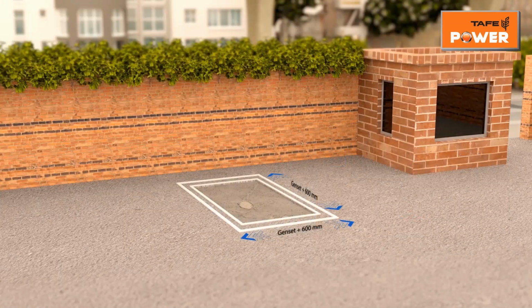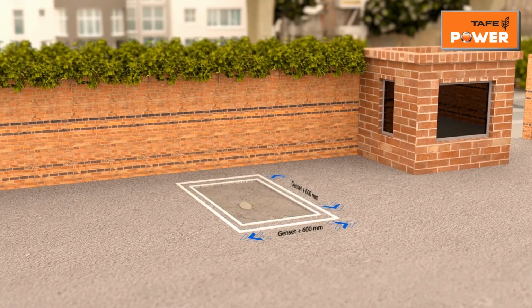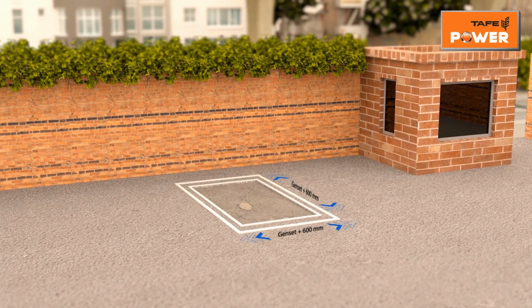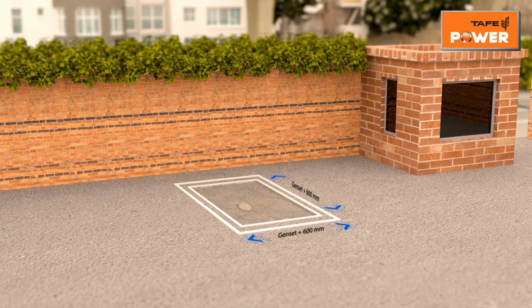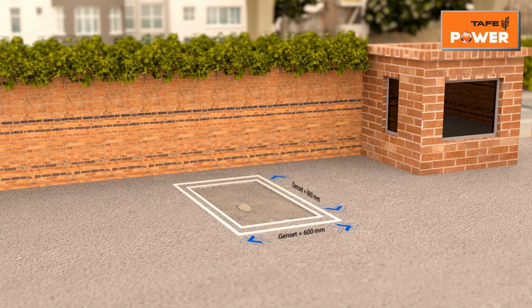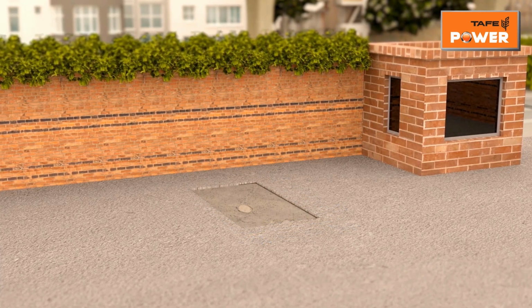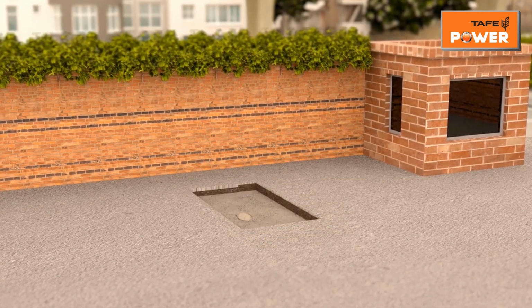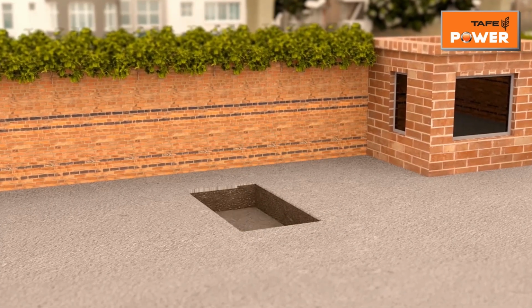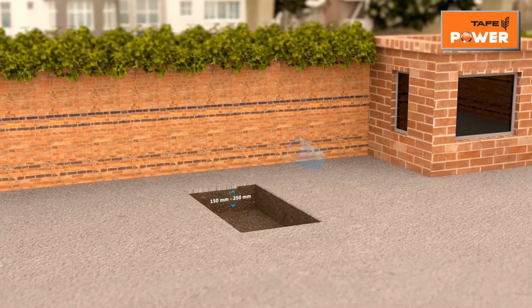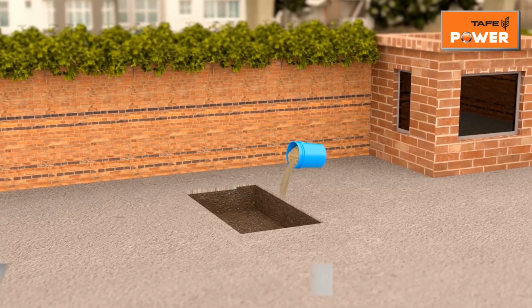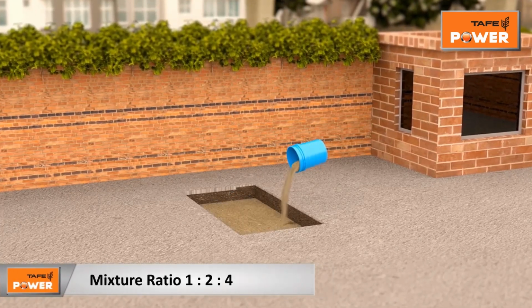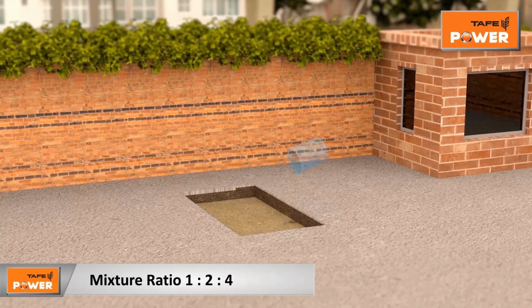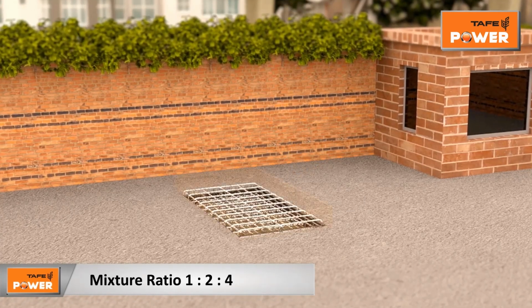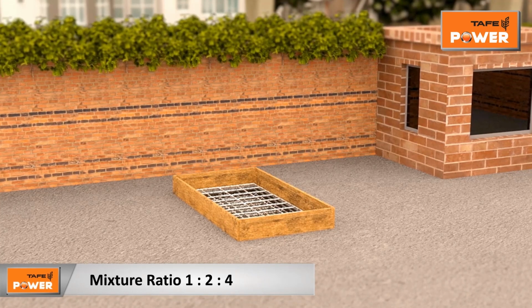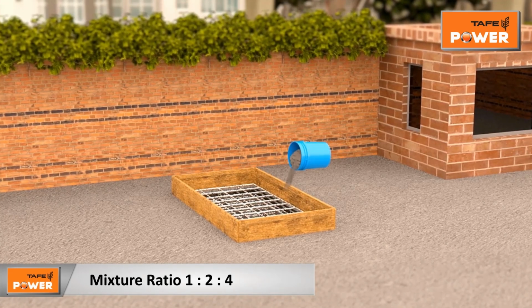Foundation. Foundation is one of the important factors affecting the successful operation and life of genset. The length and width of the foundation should be 600 mm more than that of the DG set size, that is 300 mm on each side. Genset foundation should be 150 to 250 mm below the ground level, depending upon the soil condition. For preparing PCC foundation, use a mixture of cement, gravel and sand in the ratio of 1:2:4. For RCC foundation, iron bar of suitable size should be used.